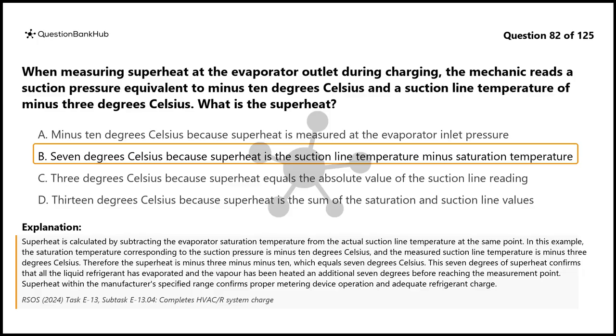This 7 degrees of superheat confirms that all the liquid refrigerant has evaporated and the vapor has been heated an additional 7 degrees before reaching the measurement point. Superheat within the manufacturer's specified range confirms proper metering device operation and adequate refrigerant charge.